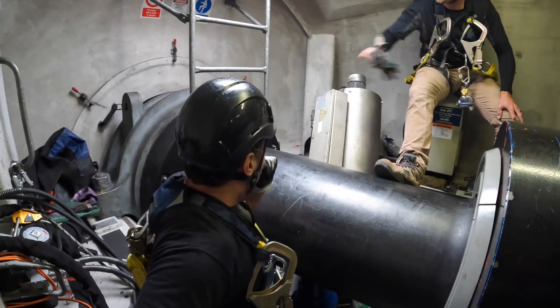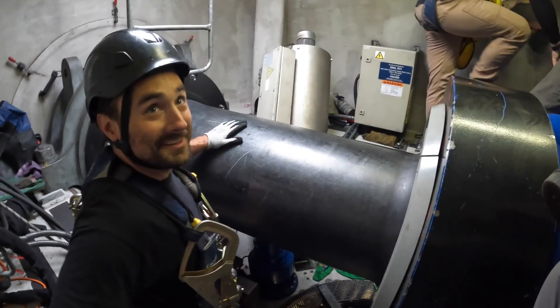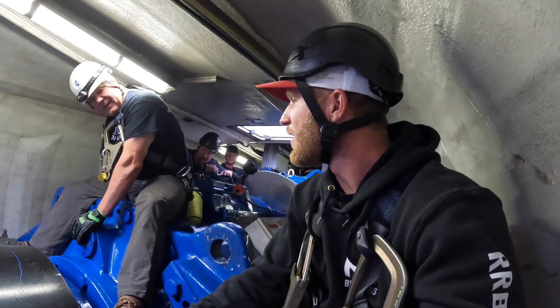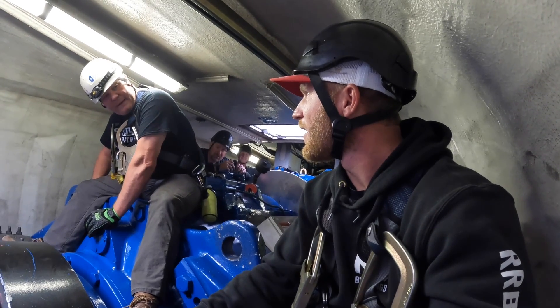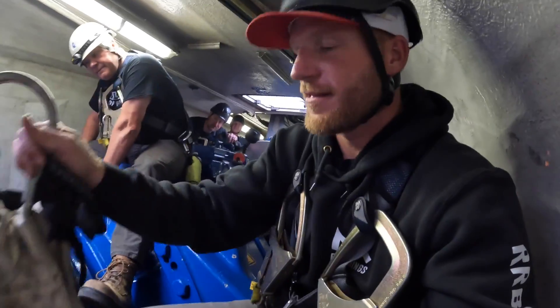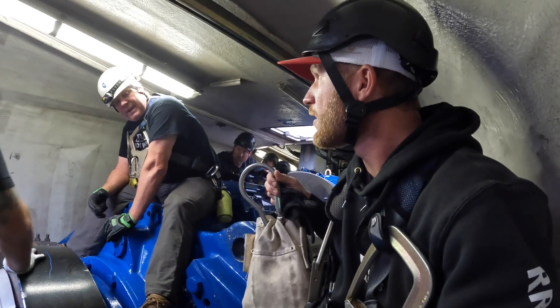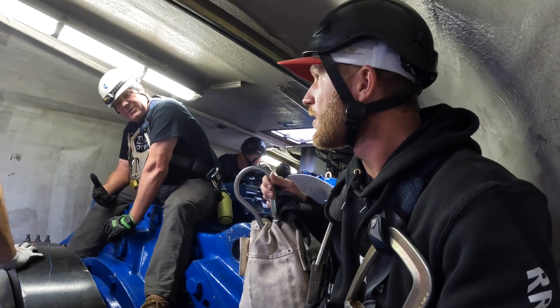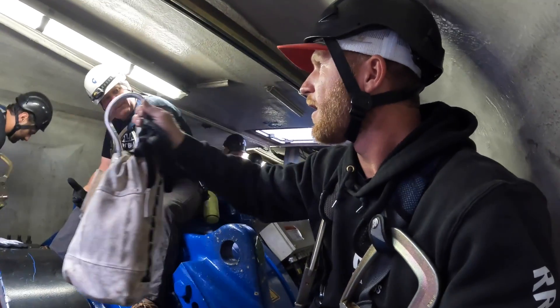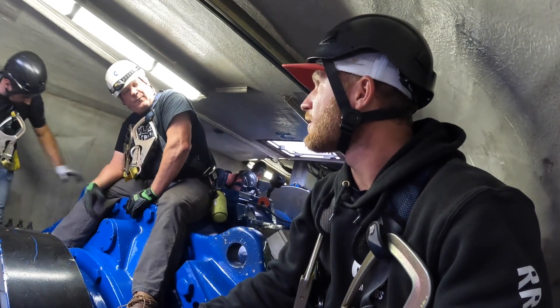Wow. We're closing. There's a lot of room over here. The front side will be like 14 and a half RPM, and then when it comes out on the high speed side it'll be 1,210 RPM. It's a six-pole squirrel cage generator, so it has six poles and needs to turn at 1,210 RPM to produce 60 Hertz frequency. We use 60 Hertz, so that way it can go right to the grid — just the same frequency.